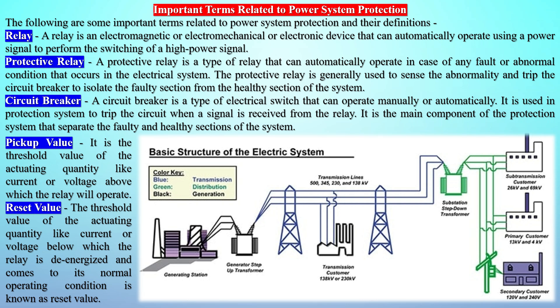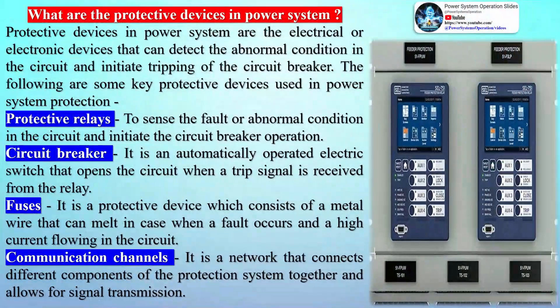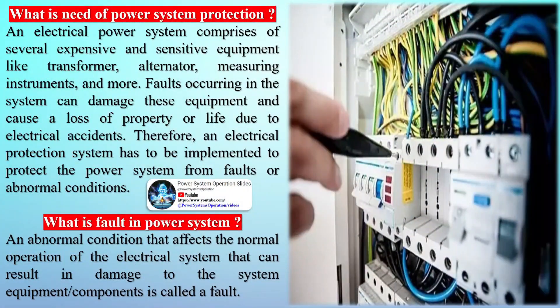The opening of faulty circuits requires some time, which may be in milliseconds — insignificant in common day life. However, the circuit breakers used to isolate the faulty circuits are capable of carrying fault currents until they are totally cleared. Circuit breakers are the main isolating devices in a distribution system and can be said to directly protect the system. The operation of relays and breakers requires power sources that shall not be affected by faults in the main distribution. Hence, batteries are a vital component in the protective system, ensuring uninterrupted power to relays and breaker coils.